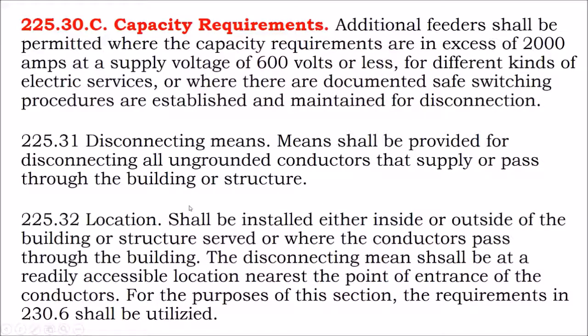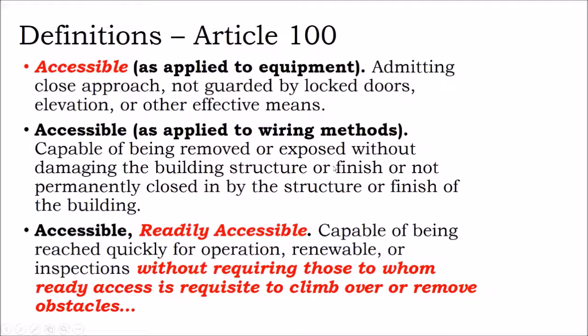Location. The disconnect shall be installed either inside or outside the building where the conductors pass through the building. The disconnecting means shall be at a readily accessible location nearest the point of entrance of the conductors. For the purposes of this section, the requirements in 230.6 shall be utilized. Well, now we have some new definitions to talk about. The first is what is accessible, and then what is readily accessible.